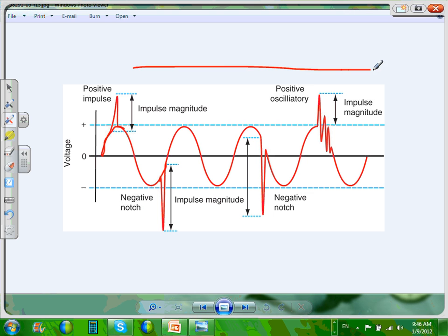So if you have a 20 amp signal like this, and you put this signal across your electronic devices, when everything is done and they're working, this is how your signal is going to look, something similar to this. The question is, who cares that my electronic equipment makes my signal go from this way to this way? They're not linear. The current doesn't match the voltage linearly. This is a bad signal because it adds to the neutral, it overloads the neutral, especially in the three-phase system.